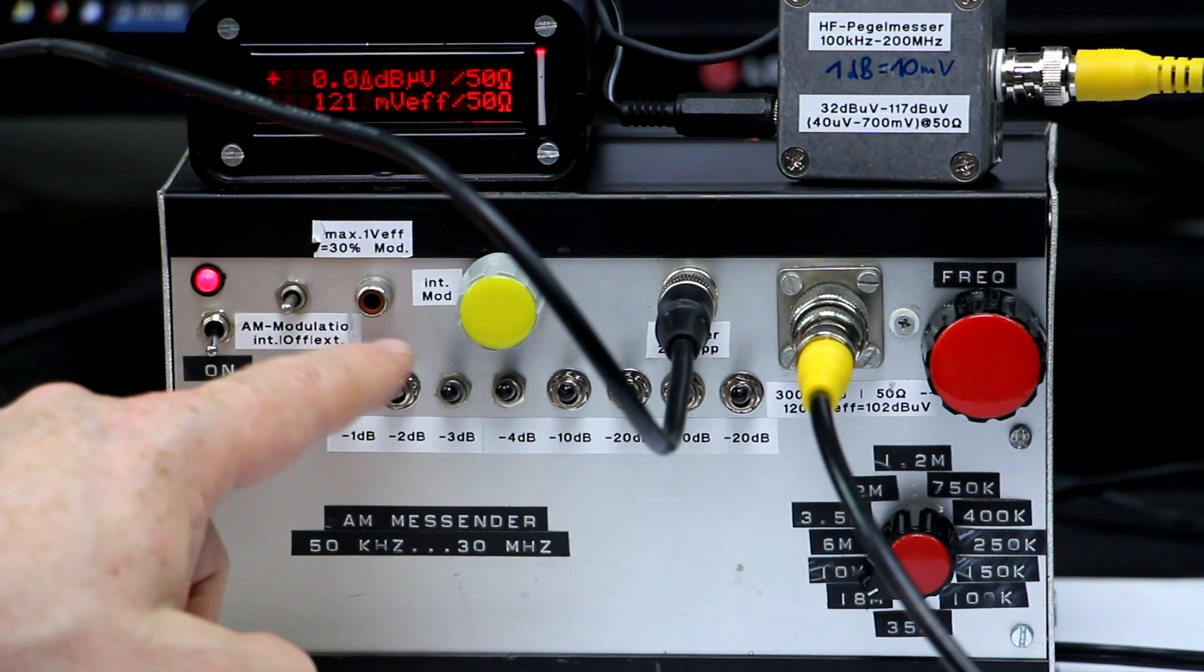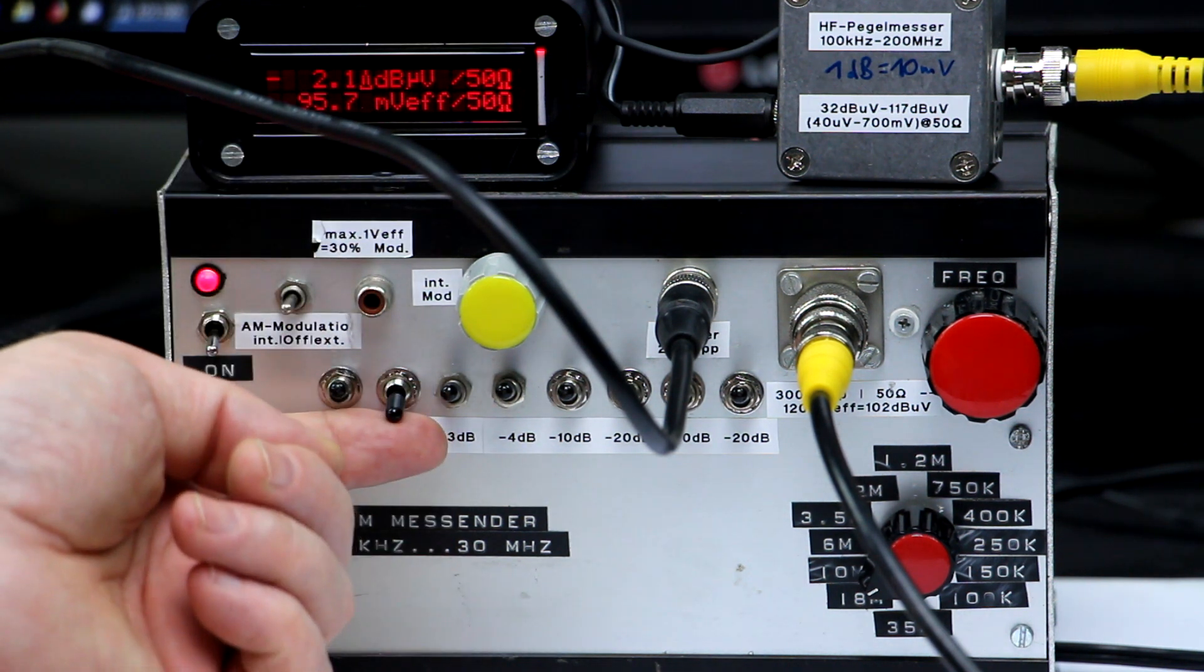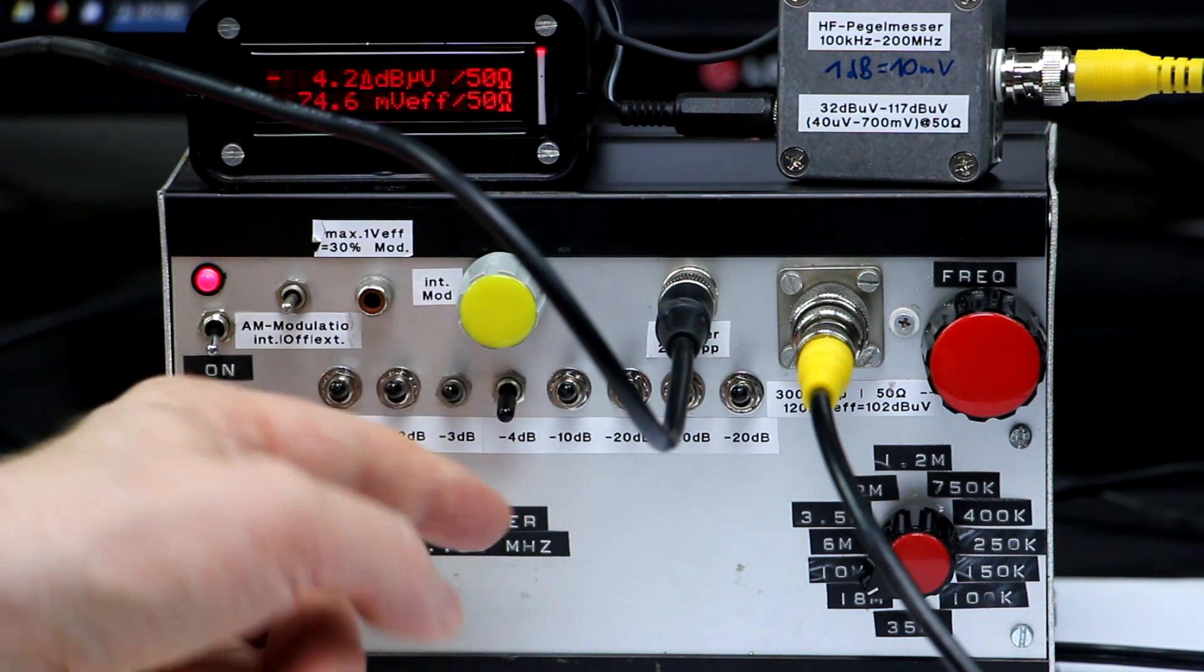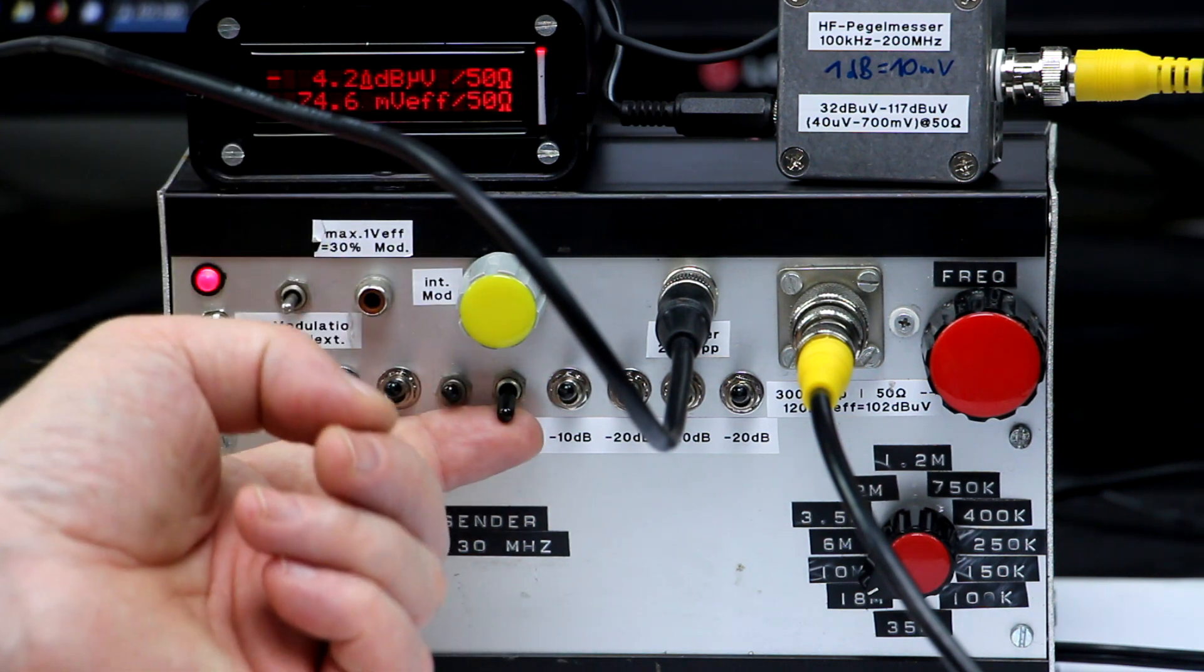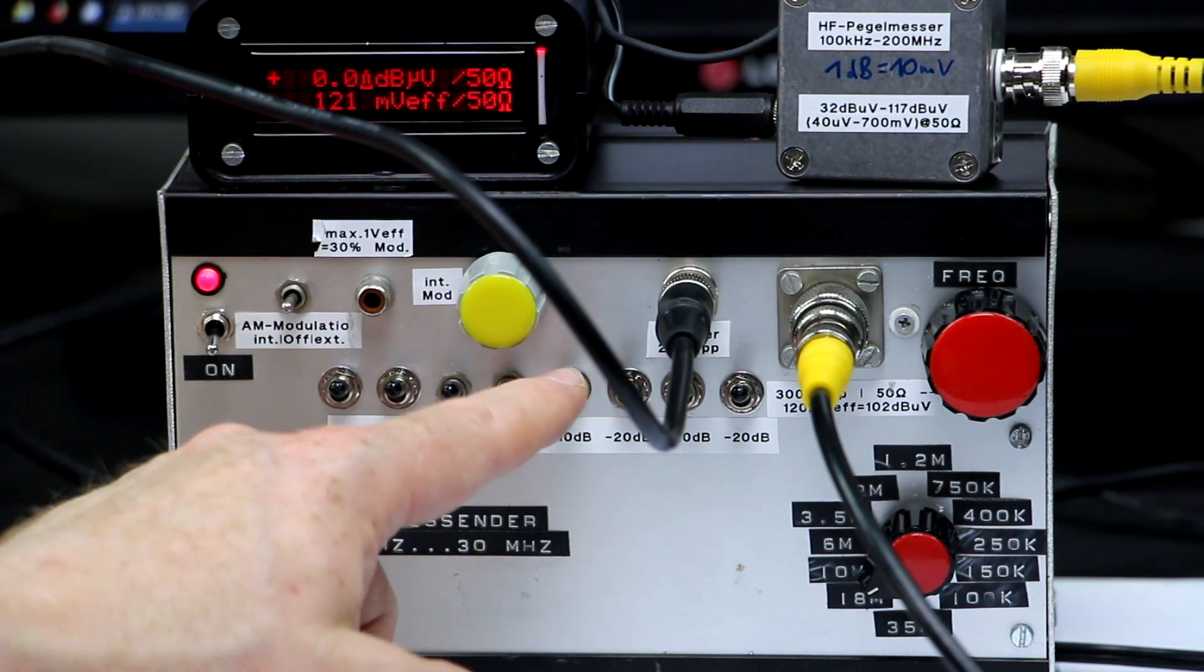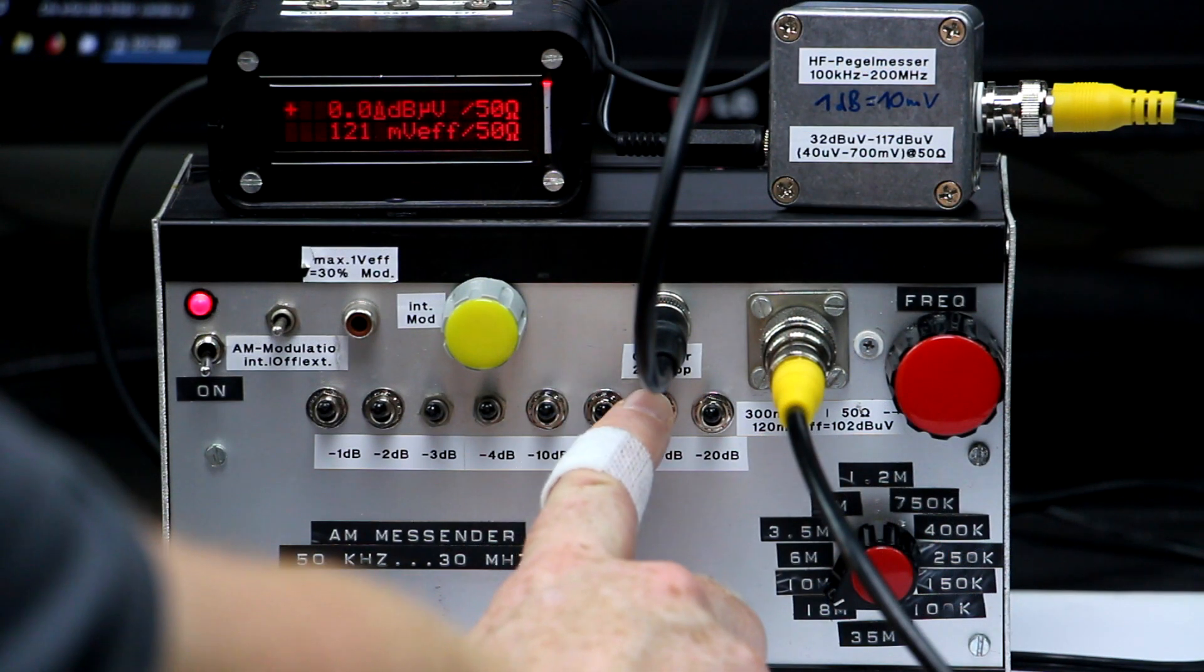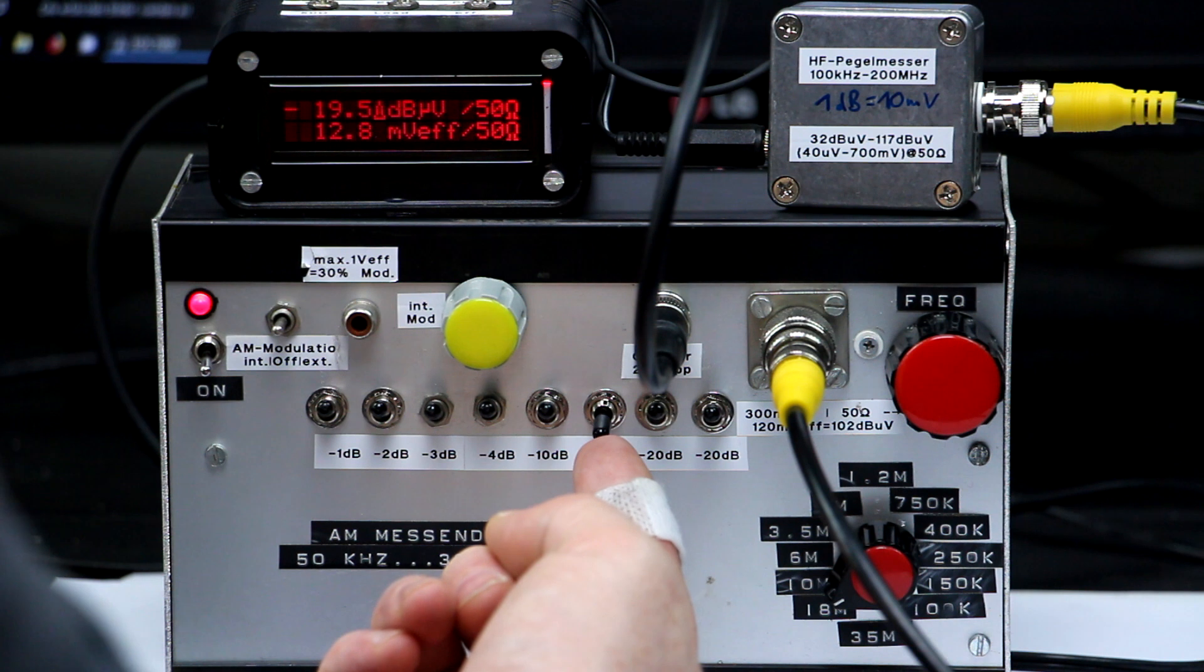The minus 2 dB gives minus 2.1 dB within spec. Minus 3 dB gives exactly minus 3. Minus 4 dB gives minus 4.2. That's okay. If we're within half a dB, then we're within the accuracy here of the log converter. Minus 10 dB gives minus 10.1. And finally, we have three identical minus 20 dB attenuators. Let's take a look. Minus 19.5.